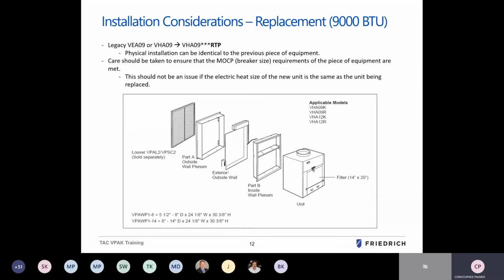If you're upsizing the heater size, you would need to make sure that the correct orientation and sizing of the wire size as well as the breaker size is appropriate to match. And then here's an example image of the different louver and plenum pieces, starting with the louver on the outside of the building, the outside wall plenum sleeve, the example of the outside exterior wall with the proper hole cut into it, and then the inside wall plenum sleeve, which would slide into and be sealed against the drywall on this side, and then your sheathing on the outside, or whatever your finished material is for your outside exterior wall. And then finally, the placement of the unit into the sleeve.